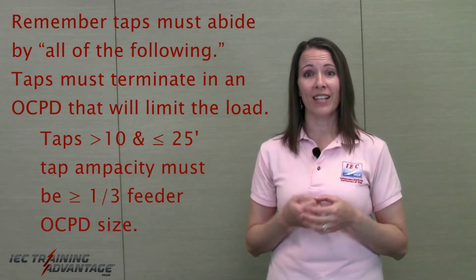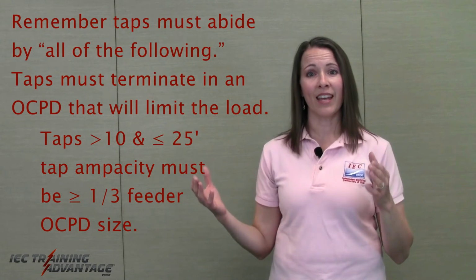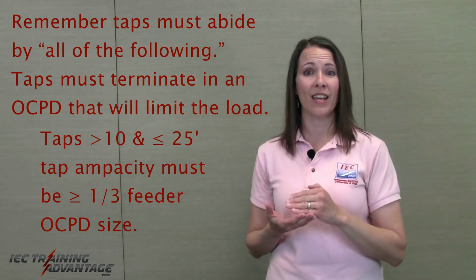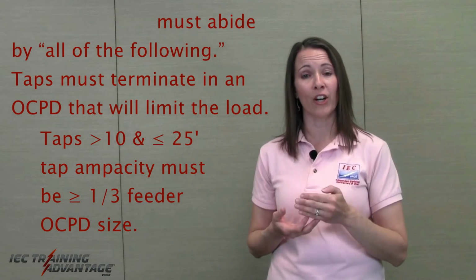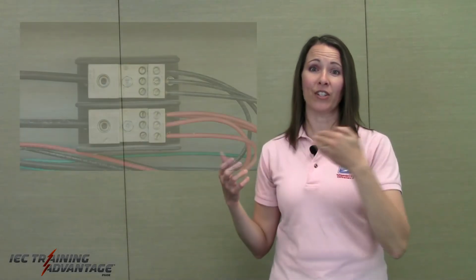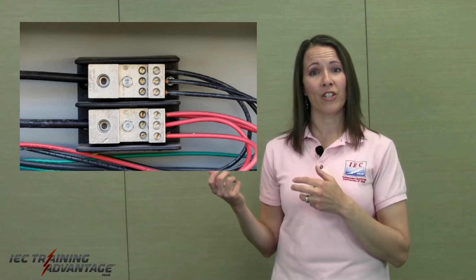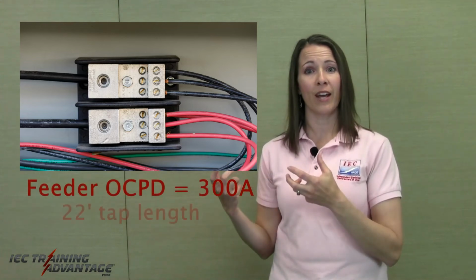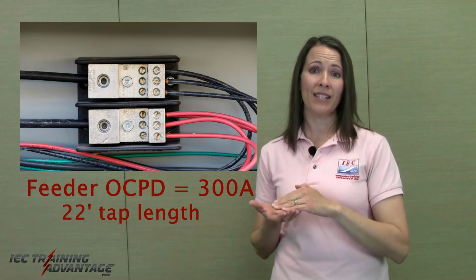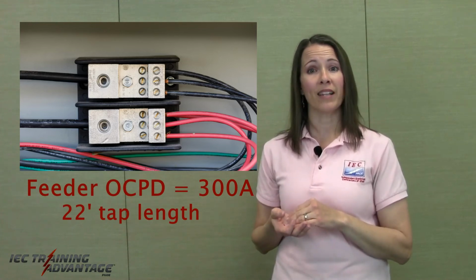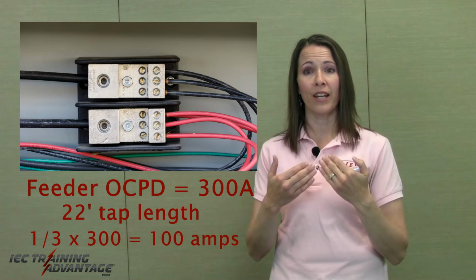The rule for this length of tap is that the ampacity has to be not less than 1/3 of the feeder overcurrent protection device. So going back to this same example, but now these tap conductors coming off of the right-hand side of that terminal lug, they are 22 feet long. Our feeder overcurrent protection device is still 300 amps, but now the ampacity of those tap conductors cannot be less than 300 divided by 3, or 100 amps.